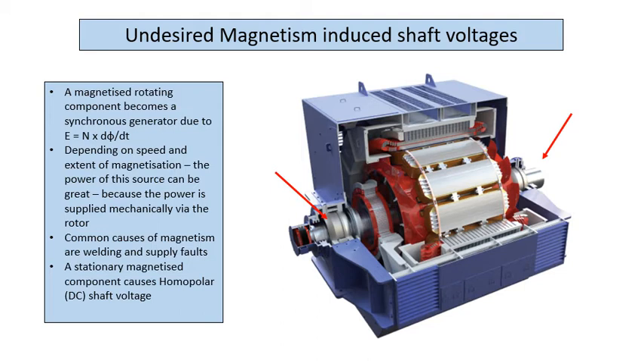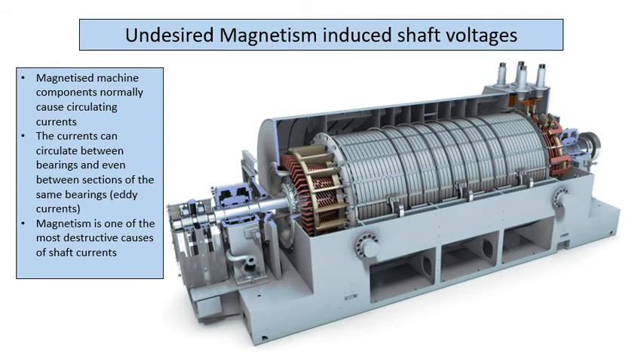demagnetized. And if you have magnetism there, for example, you can have current circulating in a very local portion of the bearing. You'll see that quite often in some bearings. You'll wonder how the current path could exist, but it's actually just a local path. So much so that you could call it an eddy current, not a full defined current path type current. And again, it's one of the most destructive causes of shaft current.